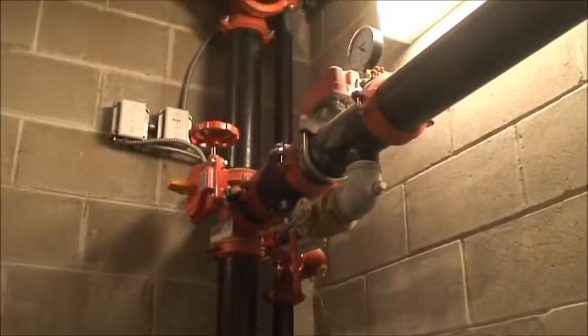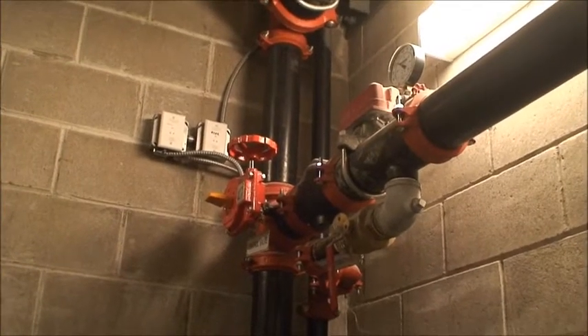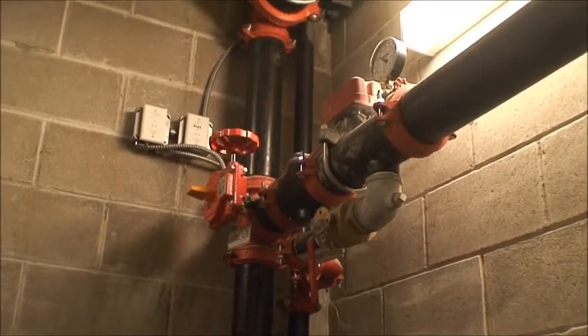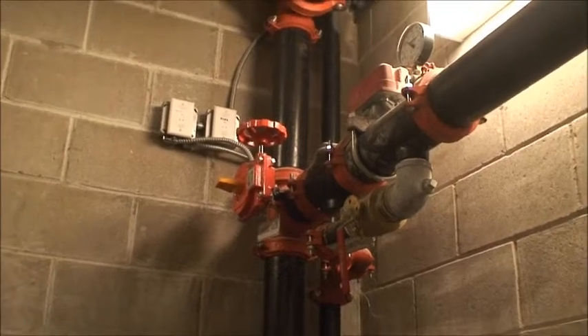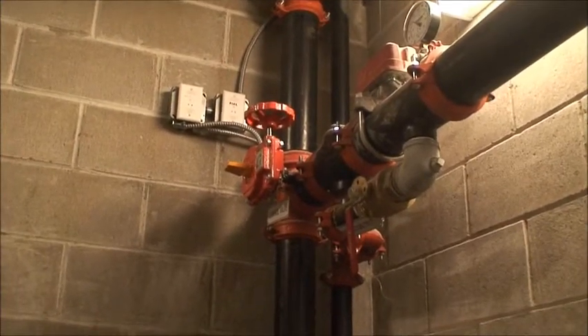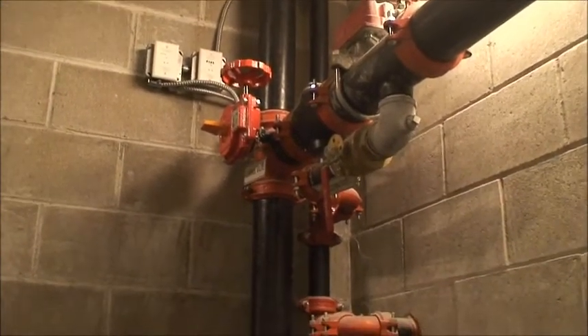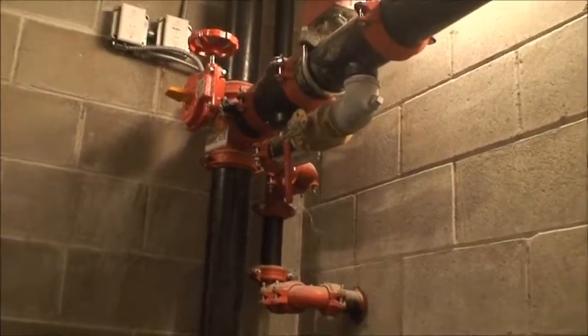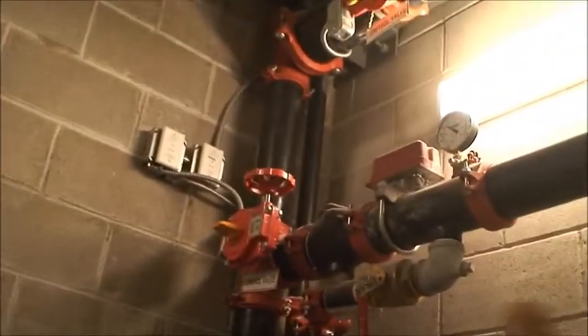Closing that up, because it won't flow if there's an alarm. So that should only be done by sprinkler contractors. They're the only ones really authorized to close the tamper switches. Okay. So if some jerk decides, on his way home from the bar, to close that up?